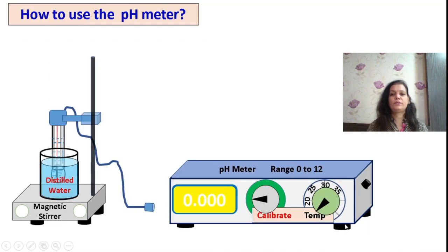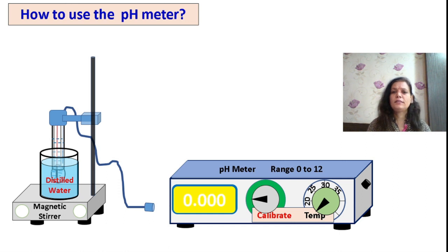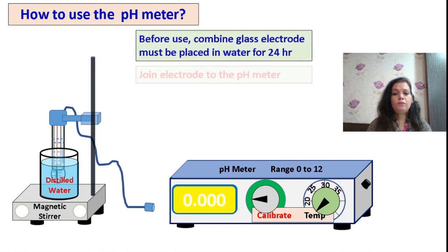When using the pH meter, always keep the electrode in distilled water to keep the membrane hydrated, as the membrane tends to dehydrate and will not function properly if left exposed. The glass electrode can be used to measure the pH of colloidal and turbid solutions and is easy to operate. However, it cannot be used at higher temperatures or for fluoride solutions. Before switching on, always attach the pH electrode to the pH meter.